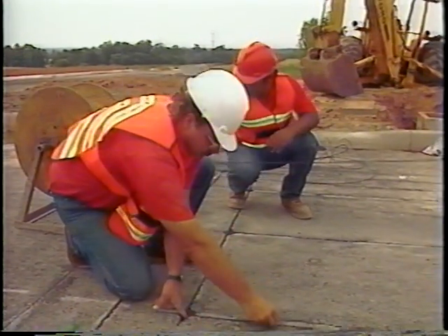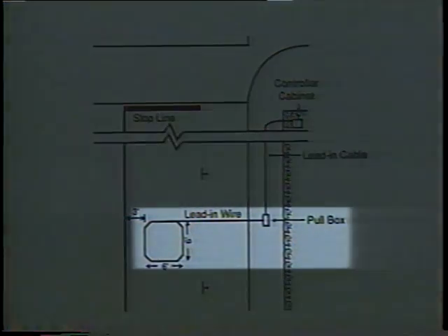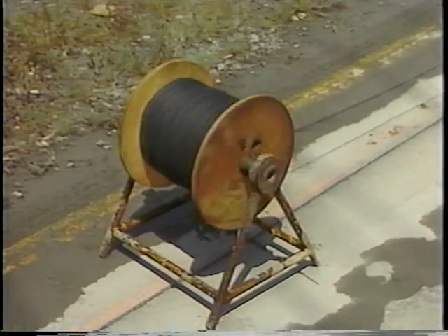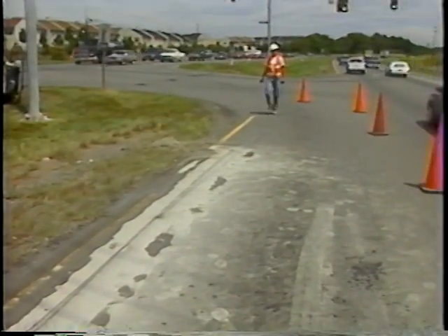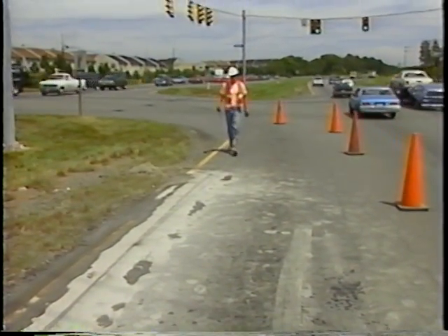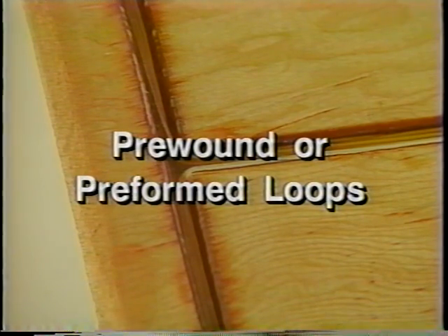Wire insertion is the next loop detector installation step. The loop must be one continuous wire from the pull box, through the curb, around the slot the correct number of turns, and back to the pull box. Check the supply reel to make sure there is enough wire before beginning, as it is very easy to lose count of the number of turns—particularly with four or more turns. Pre-wound or pre-formed loops can eliminate this possible confusion.